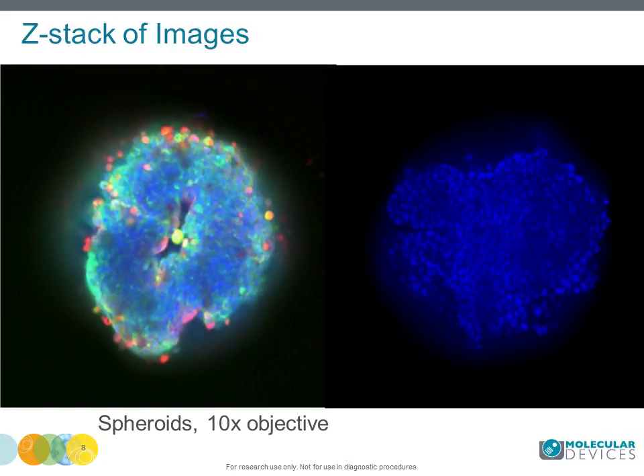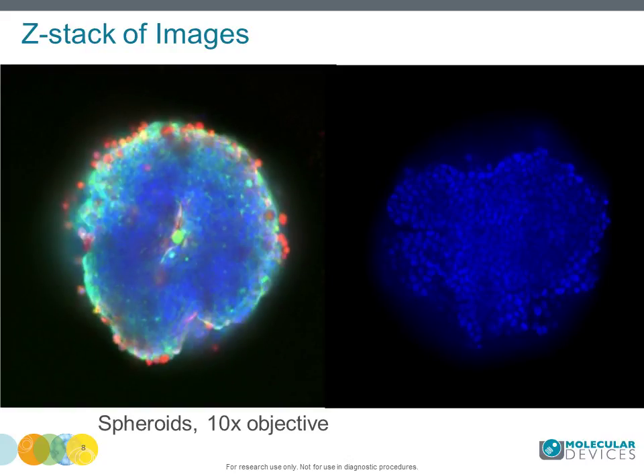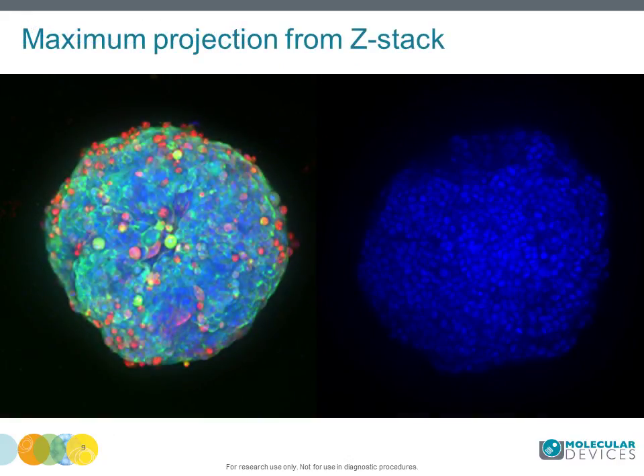The imaging system can effectively capture spheroids in a single image using a 10x objective. At 10x magnification, you can capture 10–15 images with 10-micron distance, or more than 20 images with 5-micron distance. Images can be analyzed individually in 3D mode, or this stack of images can be compressed into a 2D image using maximum projection.